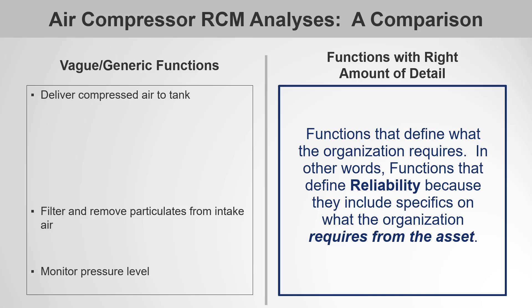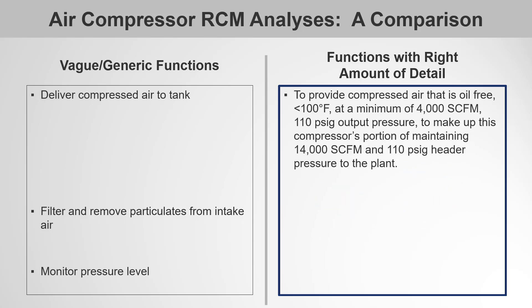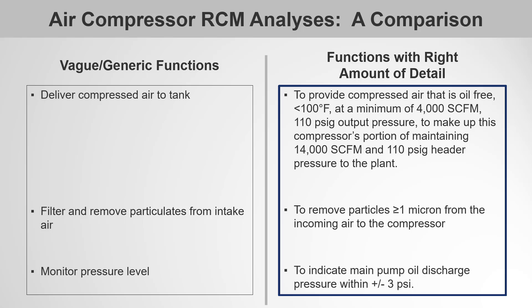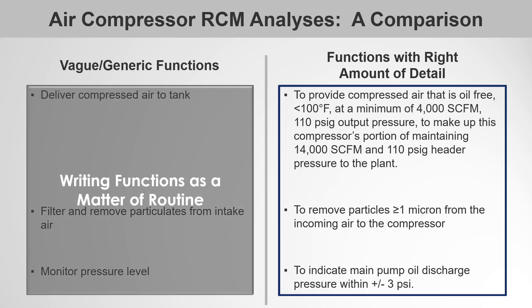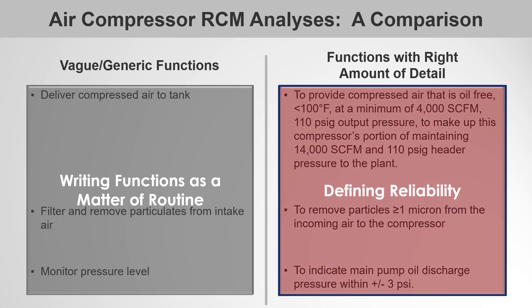Now let's look at functions that define what the organization actually requires — functions that define reliability because they include specifics. To provide compressed air that is oil-free, at less than 100 degrees Fahrenheit, at a minimum of 4,000 standard cubic feet per minute at 110 psig output pressure, to make up this compressor's portion of maintaining 14,000 standard cubic feet per minute and 110 psig header pressure to the plant. To remove particles greater than or equal to 1 micron from incoming air. To indicate main pump oil discharge pressure within plus or minus 3 psi. This is defining reliability.